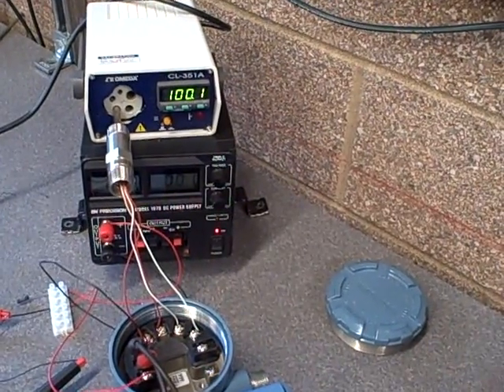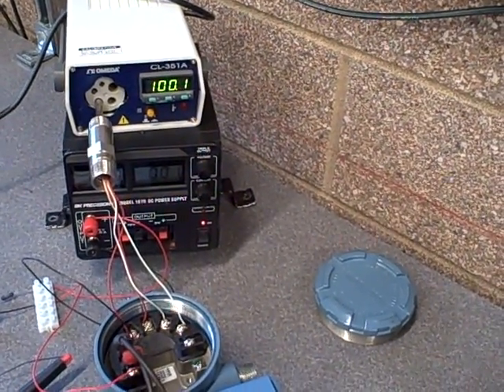So we did a two-point calibration check at 100 degrees Fahrenheit and 300 degrees Fahrenheit. Again, that's how it's done, using a dry block calibrator.